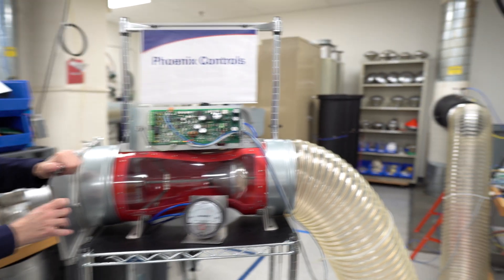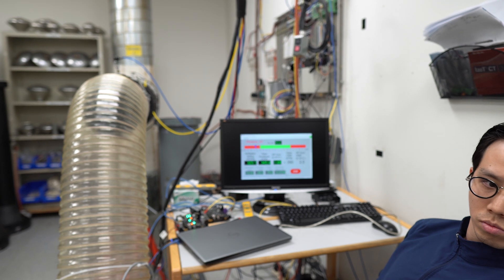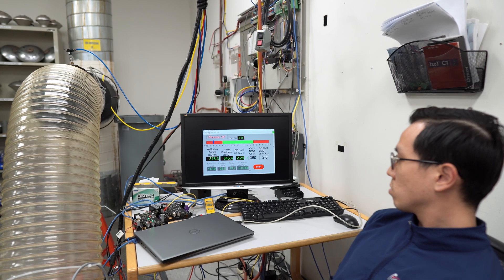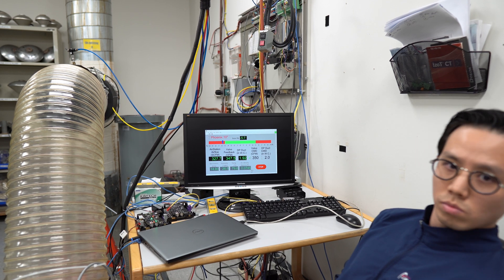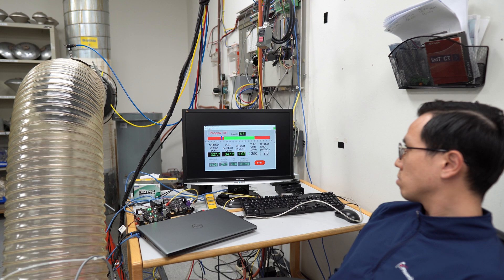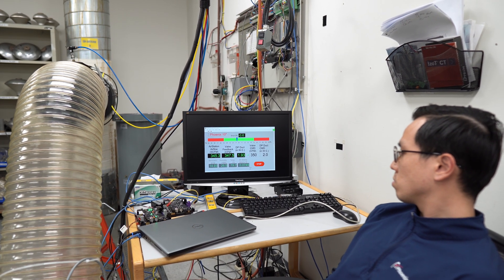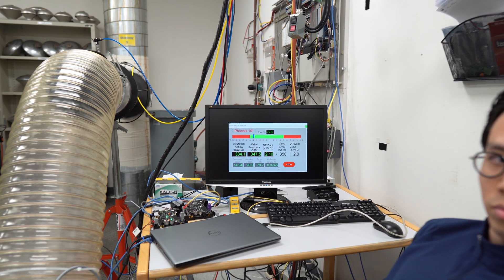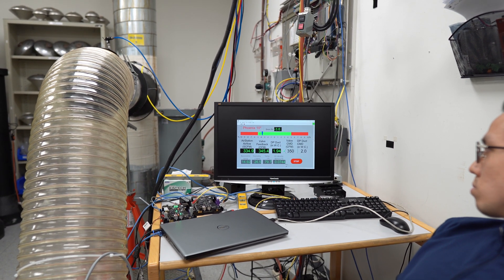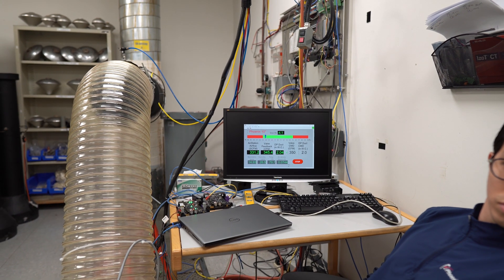I'm up at 2 inches — I'm going to drive this down to well below, going really low. Right at the bottom. I'm close to shut here. I'm 75% shut off and I'm still within plus or minus 5. If I open it up all the way, I should very quickly stay within the plus or minus 5 there as the air station tries to catch up.